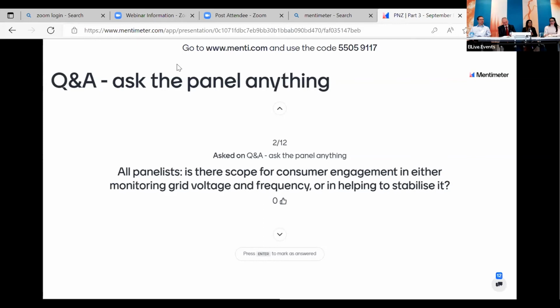In Australia, they've installed some grid forming converters and had some challenges with it. You have to be very careful when installing grid forming converters because you have to ask the right question to create a converter that gives you the right answer. Grid forming converters can also be a challenge to the network if they're not correctly designed. So all of this comes back to modeling and studies, understanding system behavior, and creating the converter, grid forming or grid following, that can contribute to system stability. Hopefully that answers the question, Kathryn.